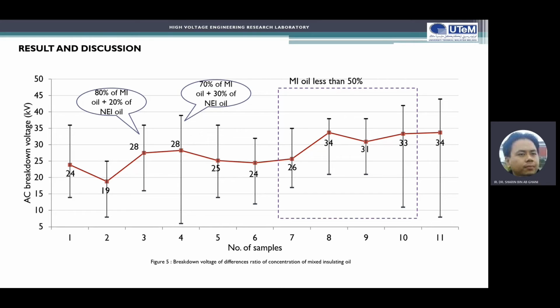This is our result in terms of breakdown voltage, or the dielectric strength measurement. Based on our methods, we have prepared 11 samples. Sample number 1 is the pure 100% mineral oil, which produced an average of almost 24 kilovolt breakdown voltage, and number 11 is the pure natural ester oil, at around 34 kilovolt. For the blending, we can refer to samples number 2 until 10.